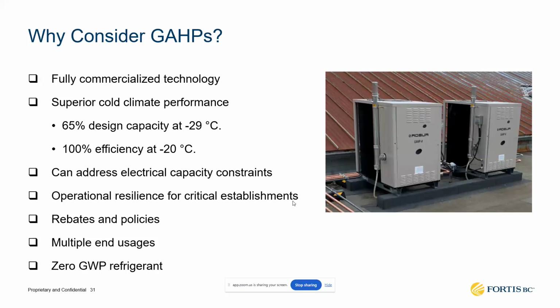Now, why consider gas absorption heat pumps? Well, it's been around for a while. It's fully commercialized, and they have representatives throughout the country. As explained to you before, it has a very good cold climate performance compared to an electric heat pump. It's not as much affected by outdoor temperature as an electric heat pump. It can provide 65% of design capacity at minus 29 degrees C, and it could be up to 100% efficiency at minus 20 degrees C. So if you have any concerns about low outdoor temperature applications, then that would be a good option.